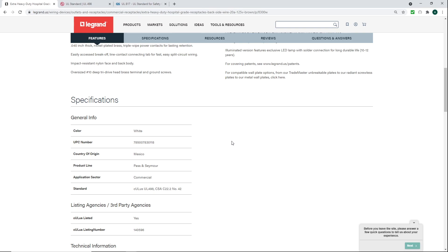Now technically, code, they're not required in the other spaces that does not have this kind of equipment. Now you might be sitting there, no no no, that's not right, we do this this way. The code book is a set of standards at a minimum. If you want to go above and beyond the minimum, there's nothing wrong with that. You can have hospital-grade receptacles in your whole entire facility because that's the way you want it. The engineer you hired for that, that's the way he likes it. There's nothing wrong with that. I'm just stating that it is not required by Chicago 2018 electrical code to be in every single space in the hospital. It's only stating that it needs to be in those certain rooms.